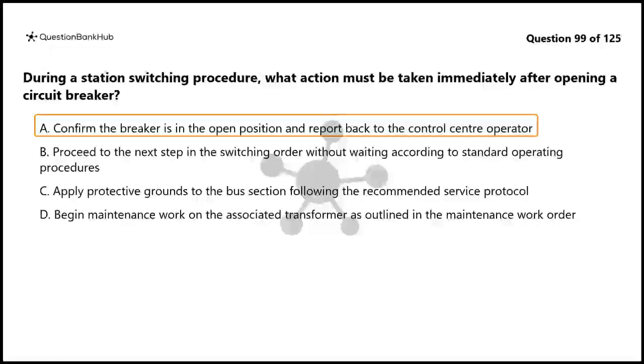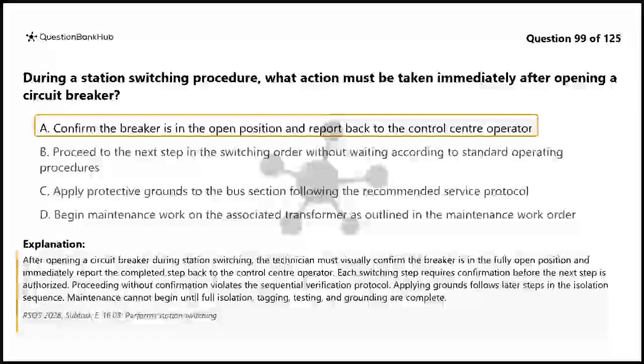The correct answer is A. After opening a circuit breaker during station switching, the technician must visually confirm the breaker is in the fully open position and immediately report the completed step back to the control center operator. Each switching step requires confirmation before the next step is authorized. Proceeding without confirmation violates the sequential verification protocol. Applying grounds follows later steps in the isolation sequence. Maintenance cannot begin until full isolation, tagging, testing, and grounding are complete.